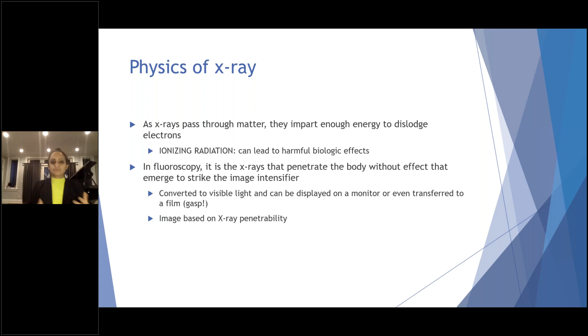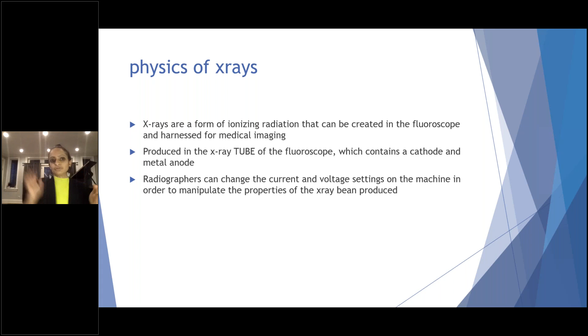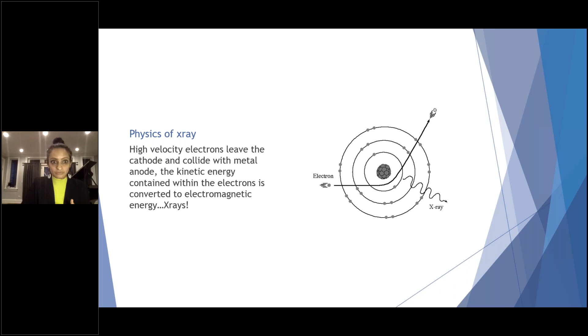All right, so X-rays are a form of ionizing radiation, just like gamma rays, that can be created in the fluoroscope and harnessed for medical imaging. They're produced in the tube of the fluoroscope. So you have a cathode that's expelling electrons from a circuit, and it focuses them on a spot on a metal anode. And it's not the entire anode, which is made of tungsten metal. It's a very small area of the anode that the electrons hit, creating an X-ray. The electrons themselves are produced and expelled by heat and heating filaments. And then when that heated electron hits the anode, we get our X-ray.